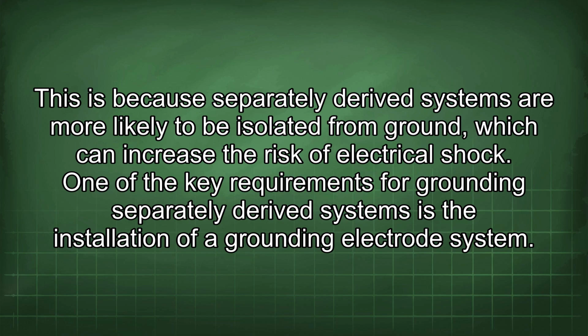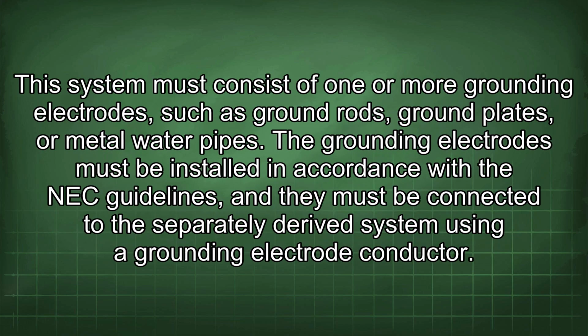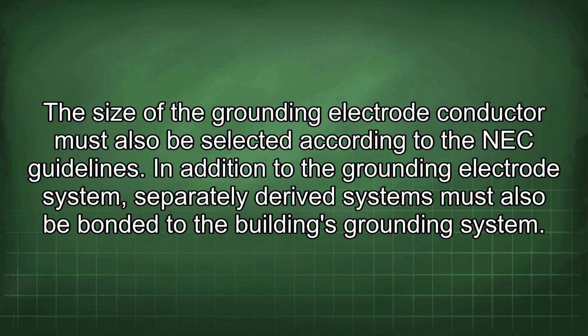One of the key requirements for grounding separately derived systems is the installation of a grounding electrode system. This system must consist of one or more grounding electrodes, such as ground rods, ground plates, or metal water pipes. The grounding electrodes must be installed in accordance with the NEC guidelines, and they must be connected to the separately derived system using a grounding electrode conductor. The size of the grounding electrode conductor must also be selected according to the NEC guidelines.